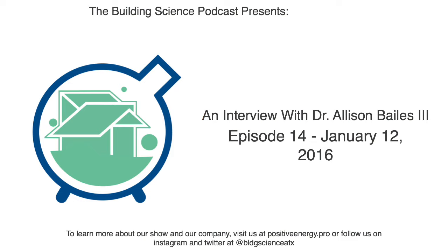You staying with these numbers, audience, out there? Yeah, it gets a little tricky to figure this out. But remember, we're basing this on ASHRAE 62.2, which is a standard that is evolving, like all standards do. Every 3 years they come out with an update. The 2010 version is, in a lot of people's mind, the ideal version because it's a good amount of ventilation. It seems to do the trick for a lot of places. And the 2013 version upped that significantly.